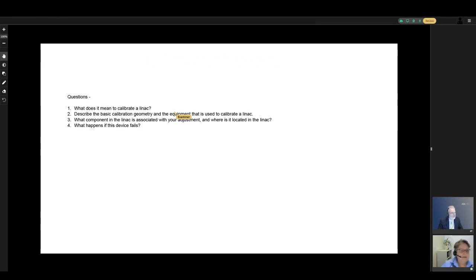So calibrating a LINAC is really the process of establishing a point somewhere in space where you know exactly where 1 centigray is, and then you correlate this with what the LINAC reads. So the LINAC understands the monitor unit versus 1 centigray. So you calibrate it such that 1 centigray equals 1 monitor unit.